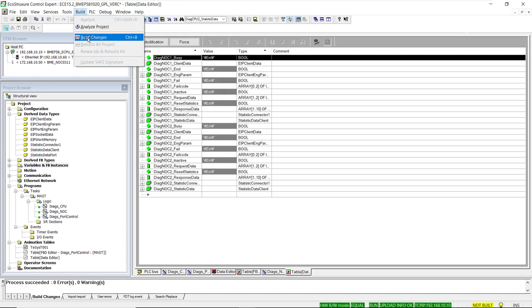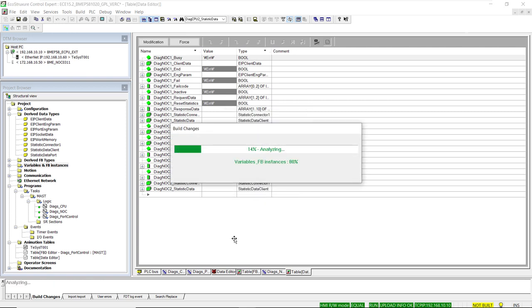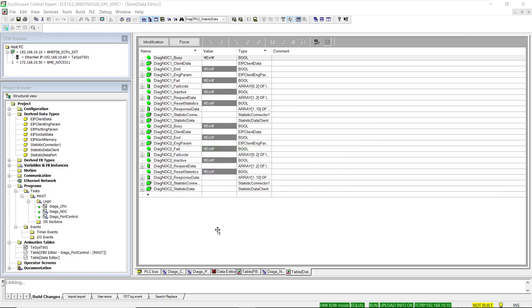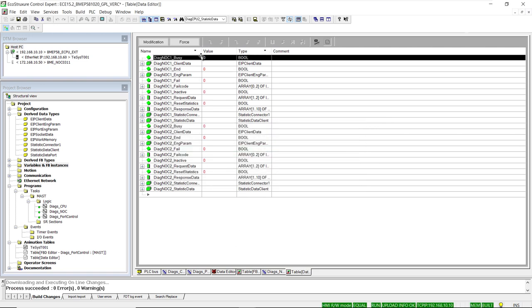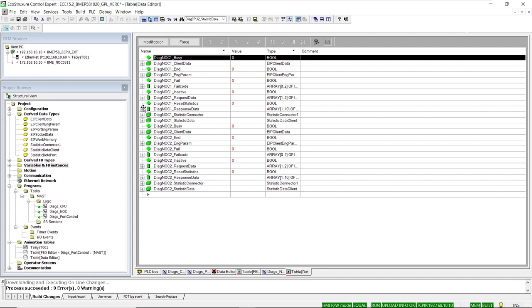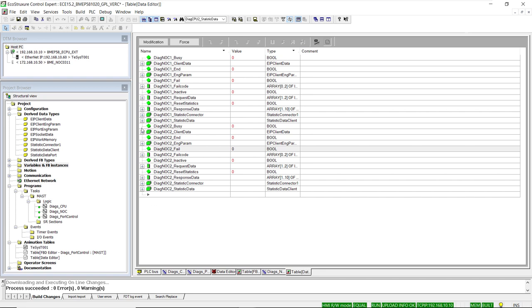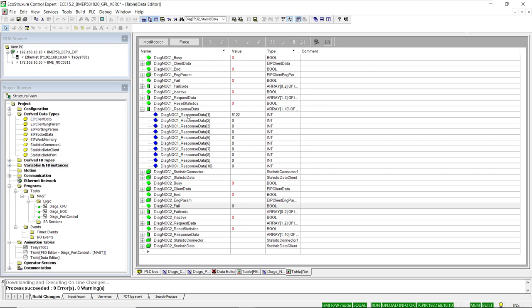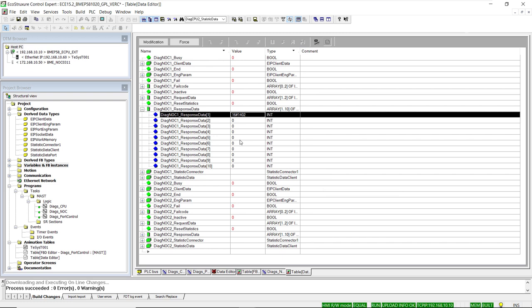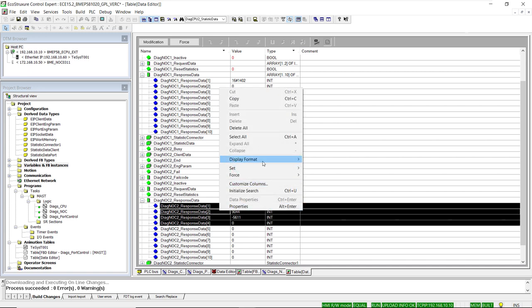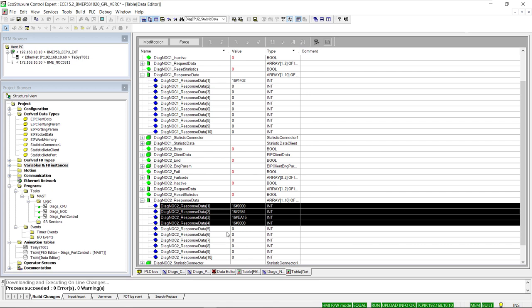We build and download the changes to the PLC while connected online. An interesting detail: during the proof of concept on a test bench, having nothing connected to the Ethernet ports of the NOC module resulted in zeros being returned. As soon as a device was connected to the NOC module's Ethernet ports, the results came as expected. Setting the display format to hexadecimal, we can correctly interpret the NOC firmware as major revision 2 and minor revision 20 (hexadecimal 14), so firmware 2.20. The MAC address is also correctly interpreted in hexadecimal.